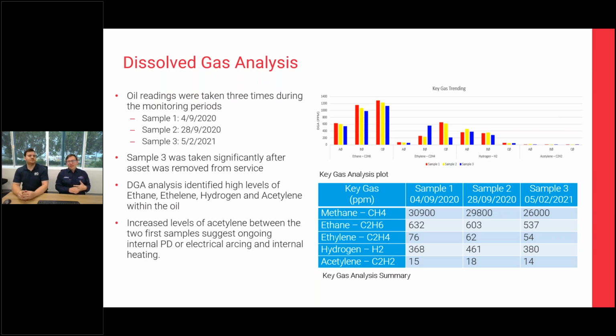So looking further into the dissolved gas analysis. Those that have been around HV assets know that dissolved gas analysis is one of those proven techniques of identifying what occurs within oil-filled equipment. Samples were taken periodically over its operating life after we found the initial acetylene buildup, and we can see the trend of it. Some gases trend down, some gases trend up in this particular case, but it is important to note that there were periods of de-energization throughout these samples. That accounts for, say, the CH4, the methane, degrading at the time. Sample 3 was taken significantly after the asset was removed from service. But we can see the general heating gases are elevated more than what we would expect: the ethane, the ethylene, the hydrogen, and the acetylene in the oil. And we can see the acetylene trending upwards over time.